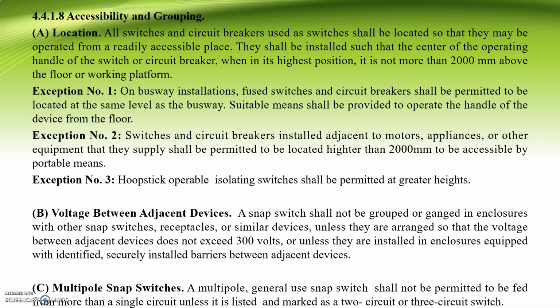Suitable means shall be provided to operate the handle of the device from the floor. Exception number 2: switches and circuit breakers installed adjacent to motors, appliances, or other equipment that they supply shall be permitted to be located higher than 2000 mm to be accessible by portable means. Exception number 3: hookstick operated isolating switches shall be permitted at greater heights. B, voltage between adjacent devices.